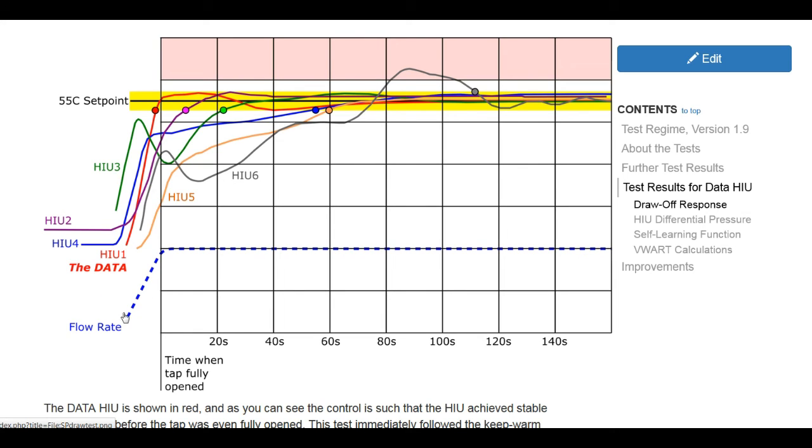Now, initially as the tap is opened, the HIUs respond, letting heat in, and the temperature of the domestic hot water increases. The idea is to get to a set point of 55 degrees C and maintain that throughout the draw-off. Now, the HIU, the data in red here, we'll see achieves a set point within a degree of 55 degrees C before the tap is even fully opened, then stays within a degree of C throughout the entire test, leveling off to within a degree of target temperature.